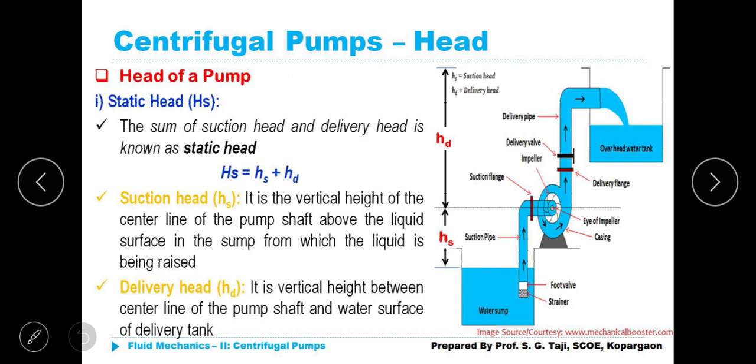As shown in figure here itself, suction head and delivery head is shown. The summation of these two is nothing but static head Hs. Hs plus Hd. What is suction head? It is the vertical height of the center line of the pump shaft above the liquid surface in the sump from which the liquid is being raised. It is very clear from figure.